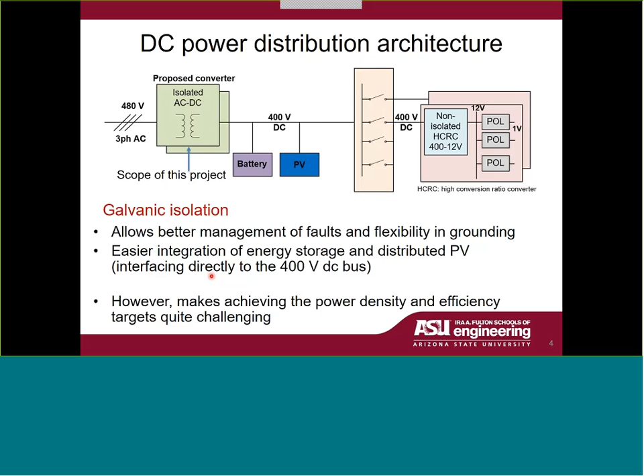The specifications for what we signed up to do as the BP4 project: input can vary from 380 to 480 volts line-to-line RMS, output is controllable between 290 to 400 volts. We will develop a 10 kilowatt system, but the real application is at a much higher power level. Our approach is to use multiple modules of this 10 kilowatt design connected in parallel to achieve the higher power level.